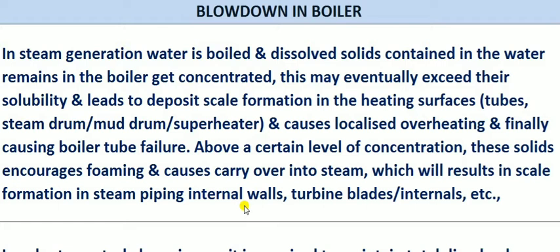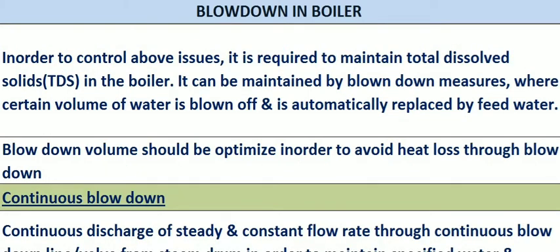We need to maintain the blowdown operation. To avoid the concentration of solids inside the boiler, we want to bleed off the water and add makeup water. However, if we do blowdown excessively, there will be energy losses because the heated water is being drained off. So the blowdown should be optimum — maintained at the quantity prescribed by the vendor or as per standards.